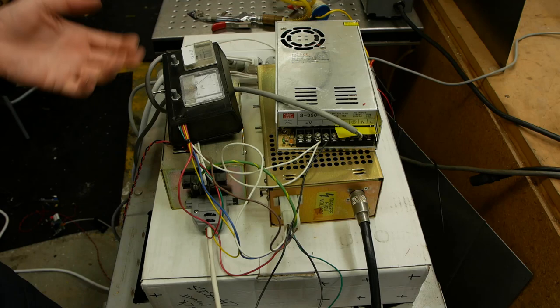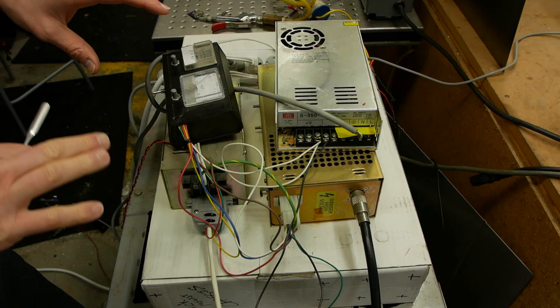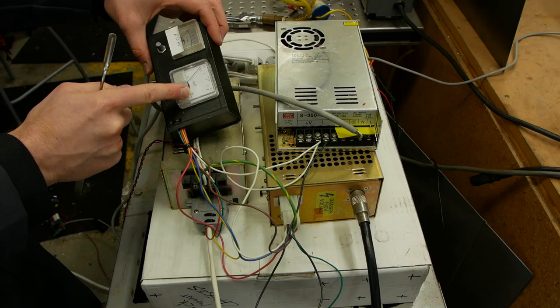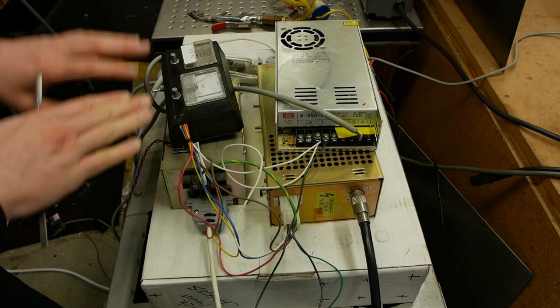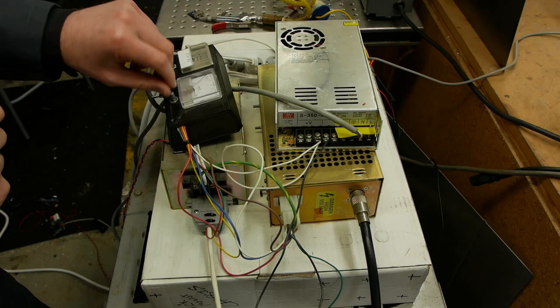So the other system drives the filament in that X-ray tube, and it's in a servo loop. So what you can do is set a desired emission current from 0 to 1 milliamp. And then the power supply increases the filament temperature by giving it more and more current until that emission current is achieved. So it's actually a nice control loop, and you can dial any amount of current you want, independent even of the voltage within the tube's operating parameters.